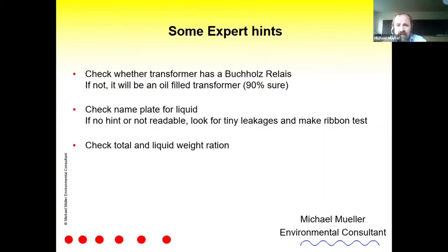If you have some problem inside the transformer and you have the formation of gas, ethene or whatever, the gas will always go up. Then it goes through the Buchholz relay, and the Buchholz relay will give an alarm and maybe even shut off the transformer, because if the transformer fails, maybe the equipment behind fails, and that is more expensive.